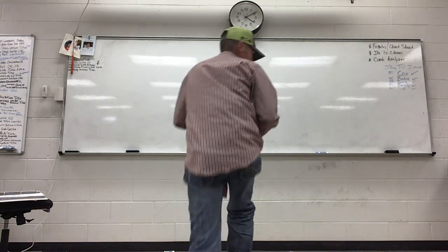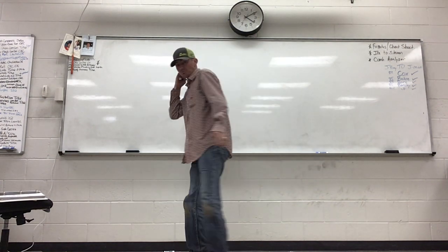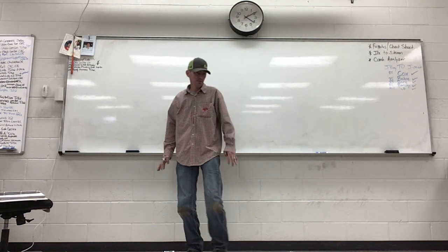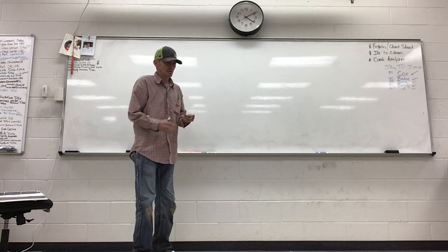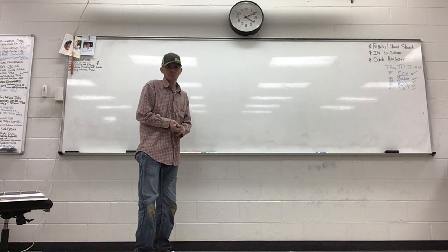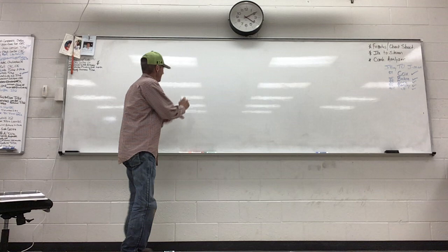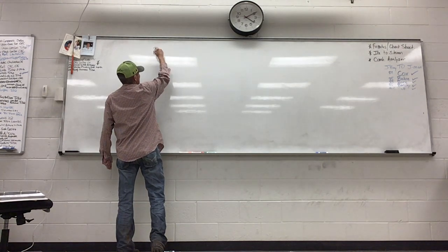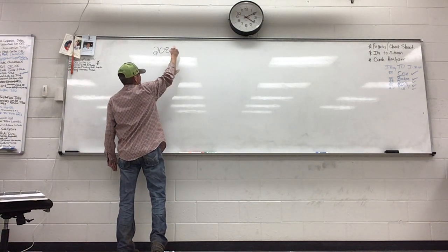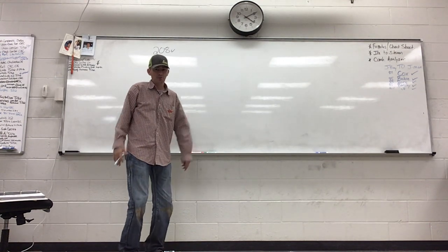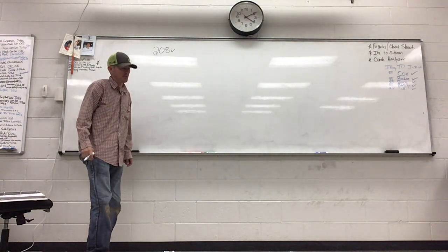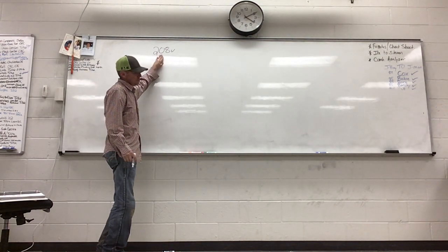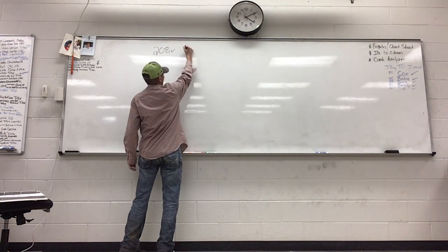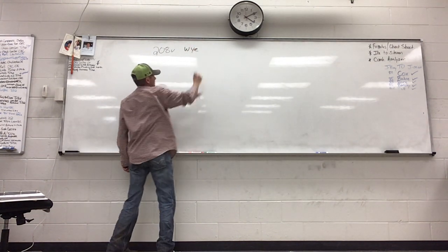Let's talk about three-phase motor and three-phase power. So when we started looking at a three-phase building, there are three pretty common voltages that we deal with. The first one is going to be a 208 volt building. Even this building we're in right now is a 208 three-phase building. This 208 is going to come off of a Y transformer, and we'll talk about that in just a second.